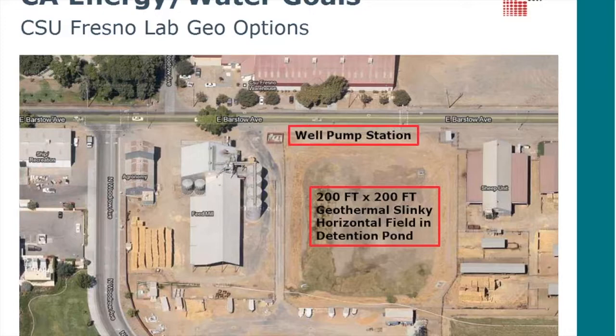So we had a couple of options. We first wanted to use the well pump and run that water through a heat exchanger. This is well water coming out of the ground that's used at Fresno for irrigation and building use, all types of uses. So you could run that water through a heat exchanger, put a heat recovery chiller on it, and get all the heating and cooling we needed. It ended up not working because we were going to affect the water temperature by about 5 degrees, and there are certain animals that just wasn't going to work for their program, so that didn't work out.